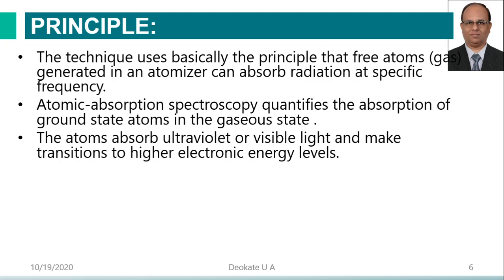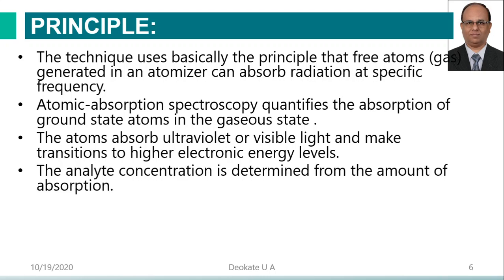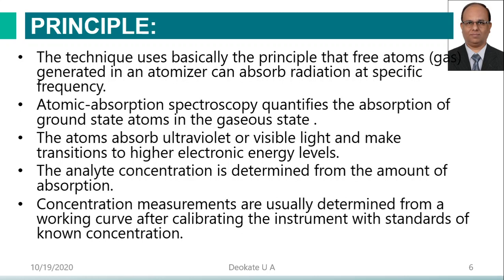The atoms in the ground state absorb radiation energies and go to the excited state. They will not remain long in the excited state and will emit excess energy as radiation — that intensity of re-emitted radiation is measured in atomic emission spectroscopy. Here, only the absorption is measured in atomic absorption spectroscopy. Analyte concentration is determined from the amount of absorption and can be used for qualitative and quantitative analysis. Concentration measurements are usually determined from a working curve after calibrating the instrument with standards of known concentration.